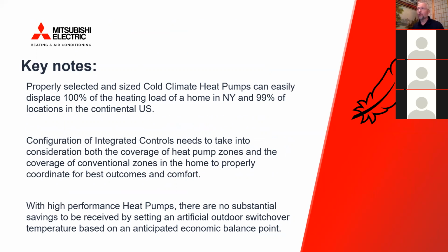So a couple of keynotes before we get too far into this. I always want to mention this because sometimes people remain skeptical about this, not only in the public but also in the contractor base. And I want to assure you that if you're selecting heat pumps and you're matching the capacity of heat pumps at the design load for your location, whatever that design load is, whatever temperature it is, that is the appropriate design load for that location and the amount of heat load. If you match that to the heat pumps, they can displace 100% of the heating load for that home. And that is absolutely positively the case in New York, particularly down in Westchester County, where it's relatively warm, to northern New England. There are homes and contractors in far northern Maine that haven't used fossil fuels in years and just depend on heat pumps.